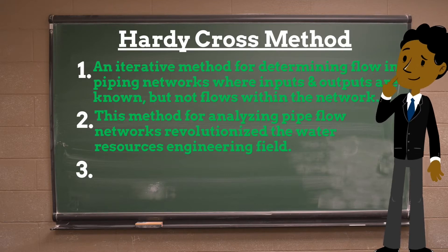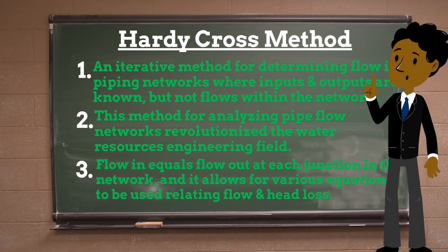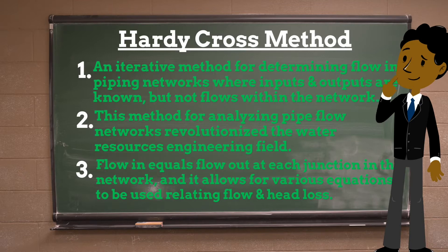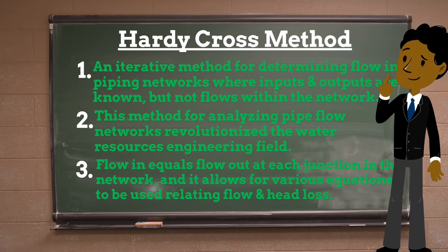Hardy Cross developed two methods for solving flow networks. Each method starts by maintaining either continuity of flow or continuity of potential and then iteratively solving for the other. The Hardy Cross method applies continuity of flow and continuity of potential to iteratively solve for flows in a pipe network. Conservation of flow means the flow in equals the flow out at each junction, and conservation of potential means the total directional head loss along any loop is zero.